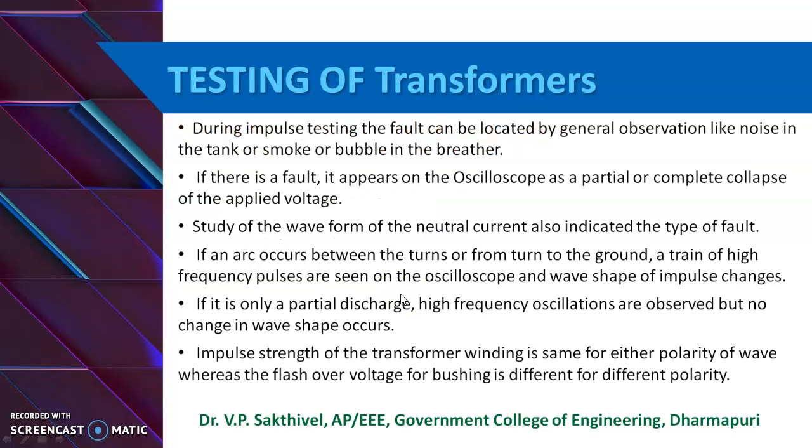During the impulse testing, the fault can be located by general observation, like noise in the tank, or smoke or bubbles that may occur in the breather.